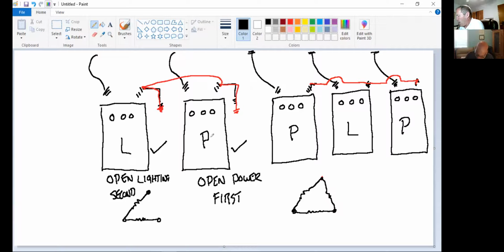Your power load transformer is feeding, and especially in open delta, is feeding a lighter load, we'll say one motor. Once I have disconnected that, the load amount is going to go down a little bit. Then I'm going to disconnect the lighting transformer with the switch, and the rest of the load comes off. So it's a load reason that I'm disconnecting that.